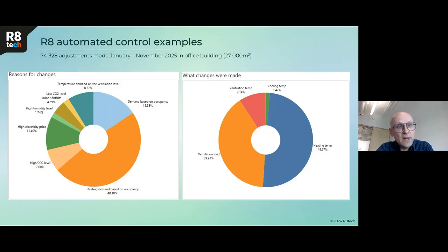These 2 graphs are showing one office building in Estonia, and our adjustments during almost 11 months. So lots of small adjustments, lots of small set point adjustments. The left side is showing the reasons for the changes: demand-based occupancy. So there are lots of occupancy-based changes. On the right side, what changes were made. So what we did, why we did it, and what we did.